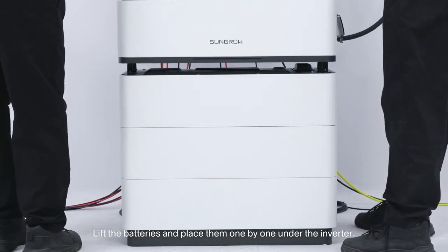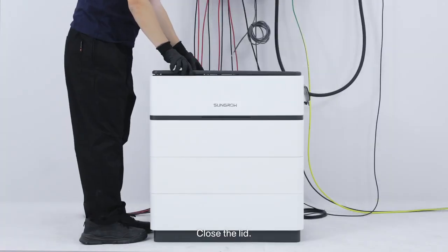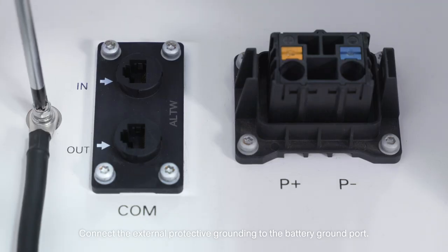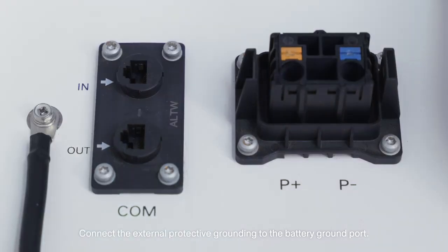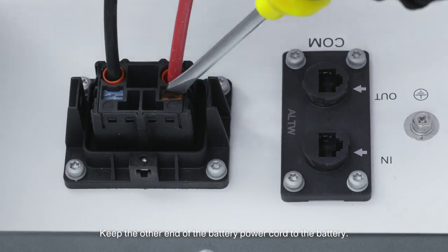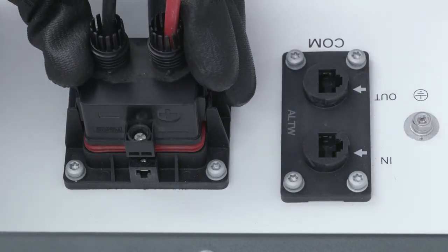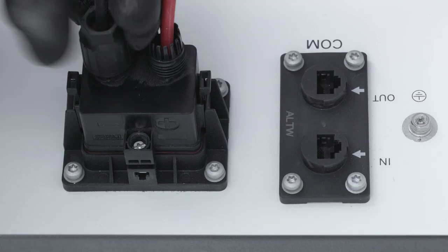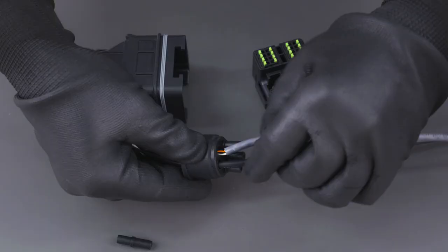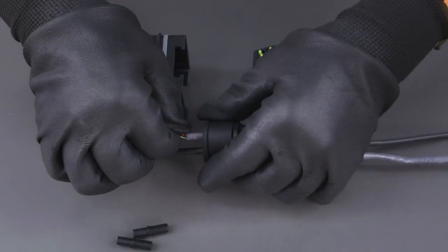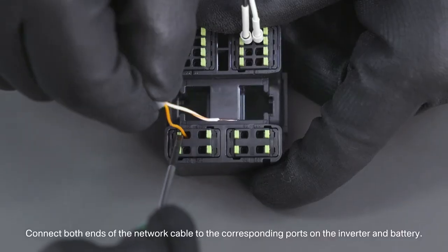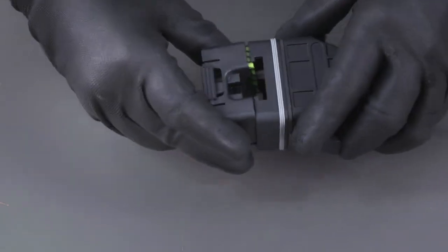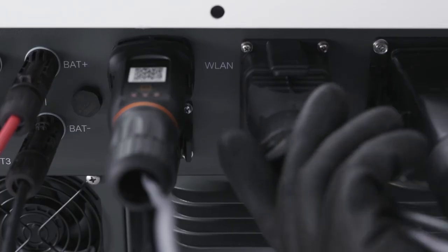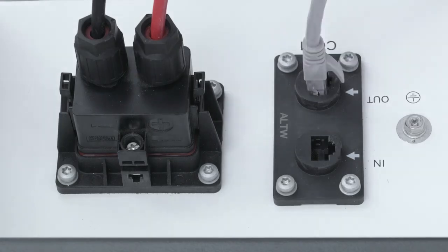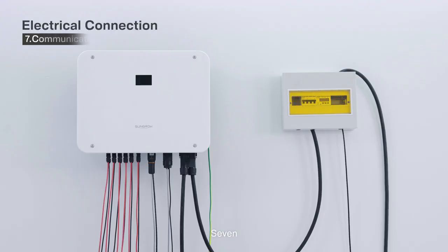Lift the batteries and place them one by one under the inverter. Close the lid. Connect the external protective grounding to the battery ground port. Connect the other end of the battery power cord to the battery. Connect both ends of the network cable to the corresponding ports on the inverter and battery. Seven. Communication connection.